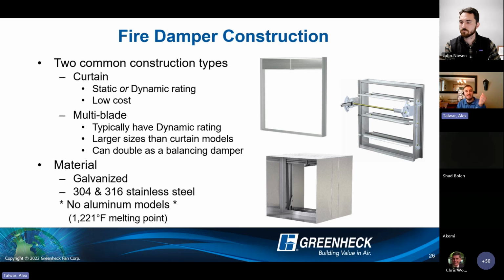You can use them as a balancing damper. They've got this manual quadrant on them, so you can set the blade position, lock it into place, and still have the spring wound shaft with the fusible link closure on it. In terms of manufacturing, we are using galvanized steel for the majority of these products. We do have options for stainless models as well. No aluminum fire dampers, due to the melting point of that particular material.